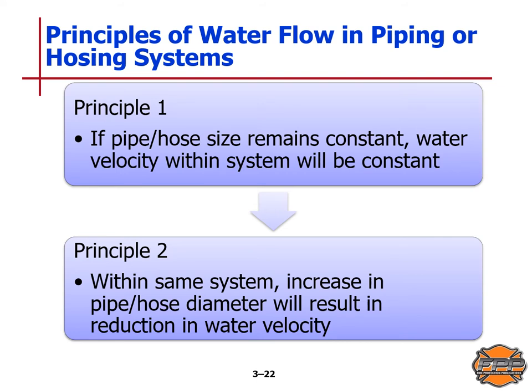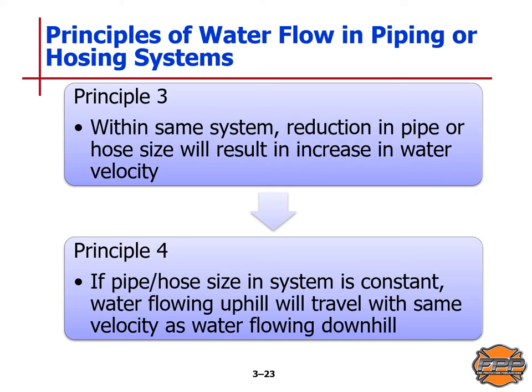Principles of water flow in piping or hose systems: Principle 1 — if pipe or hose size remains constant, water velocity will be constant. Principle 2 — an increase in diameter results in a reduction in velocity. Principle 3 — a reduction in pipe or hose size results in an increase in velocity. Principle 4 — if size remains constant, water flowing uphill will travel at the same velocity as water flowing downhill.